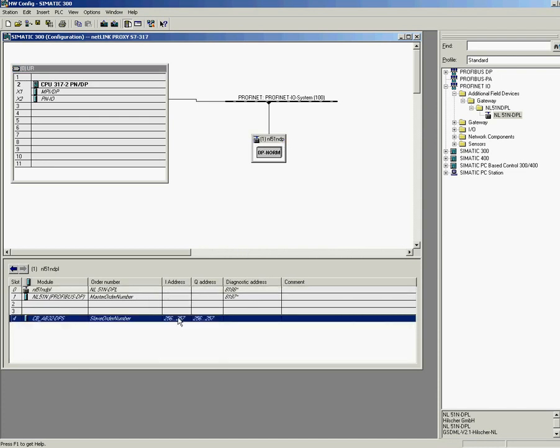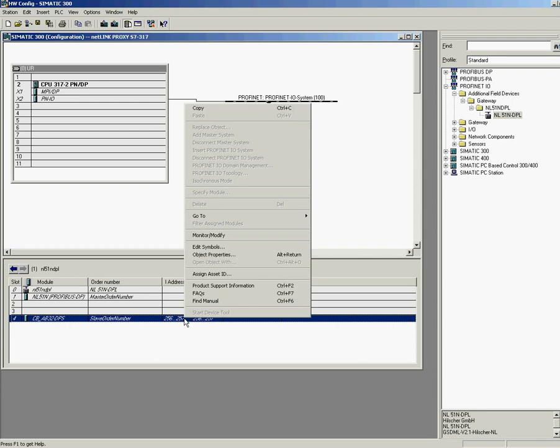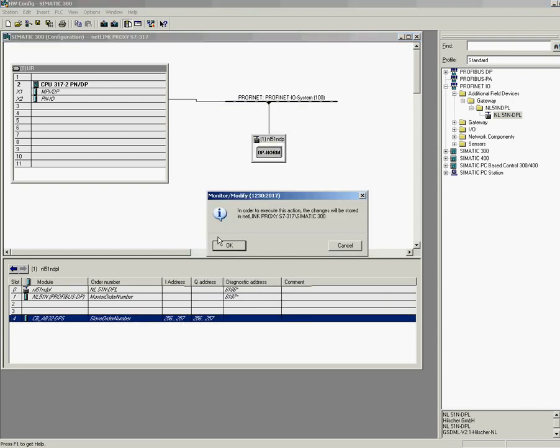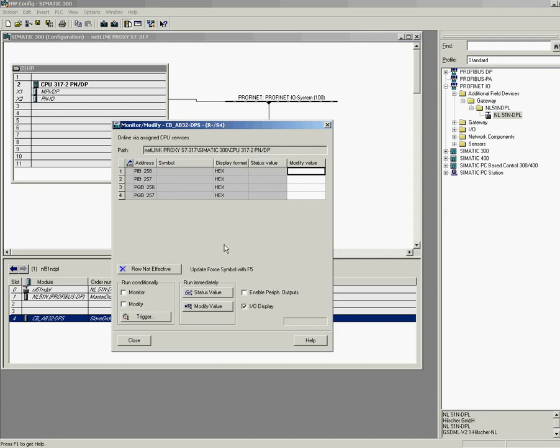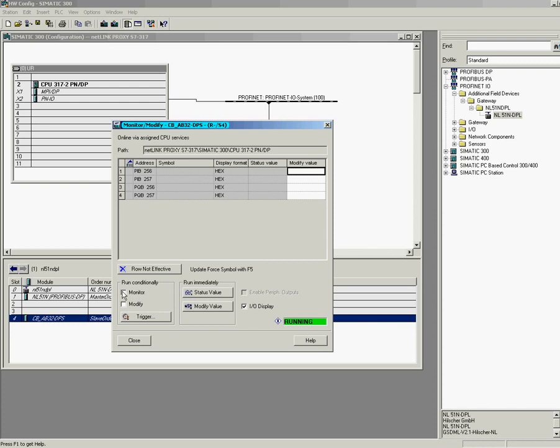So the PLC has accepted the GSDML file. And now I will make a cross-check and I will look to the I.O. data of the slave within Step7 to read some inputs and to set some outputs. Make some clicks, additional clicks here. OK, here and here. Yes. And here you see my inputs already.